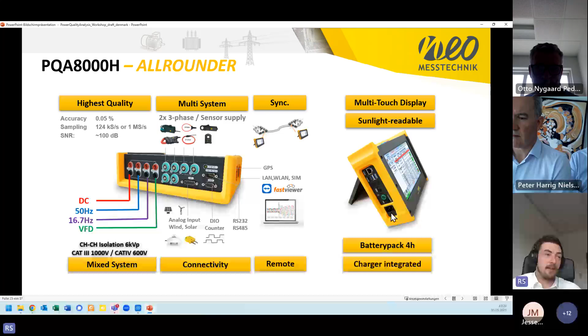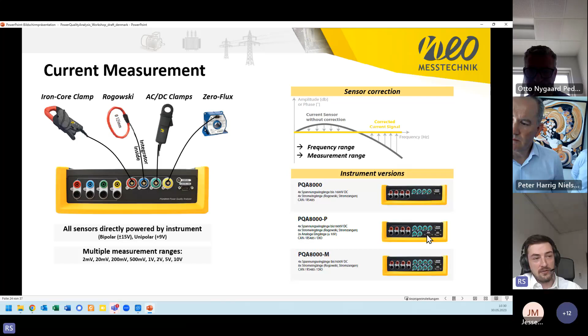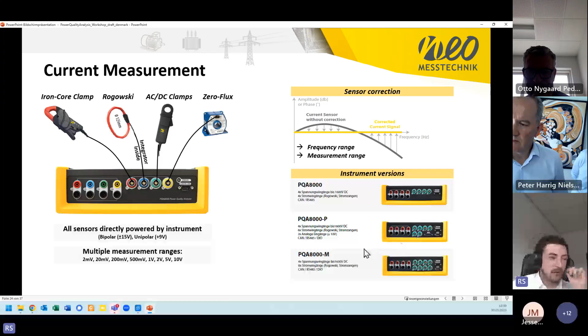Regarding the current measurement, beside the direct powered instrument by the instrument and the multiple measurement ranges from 2 millivolt to 10 volt, we have also the possibility to do a sensor correction. So through the whole frequency band, we can do an amplitude and phase correction for each sensor. Actually, we're doing this per standard for our Rogowski coils. And if it's needed, also for the really high bandwidth side, and therefore we achieve a really high accuracy also in the high bandwidth. Okay, and for the instrument versions, we have 4 current inputs, 6 current inputs with analog in or digital in, or 8 current inputs actually. So these are the types of these.